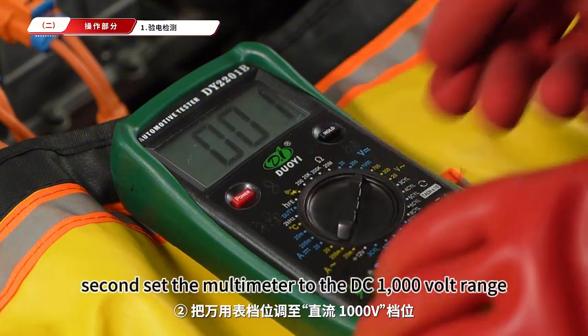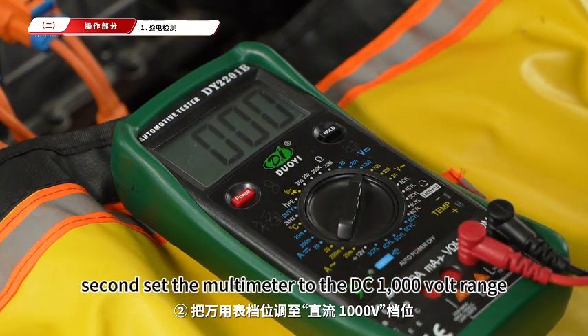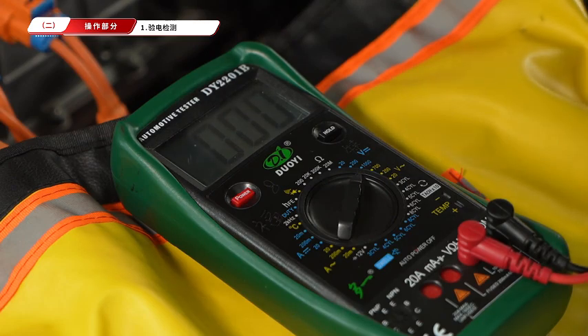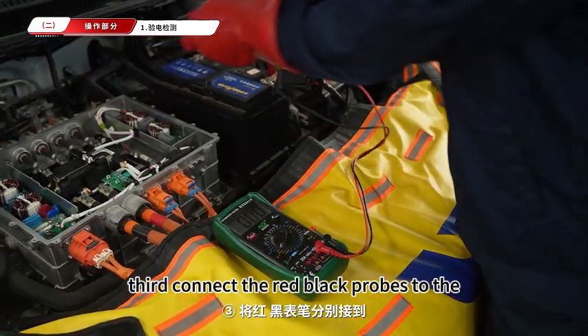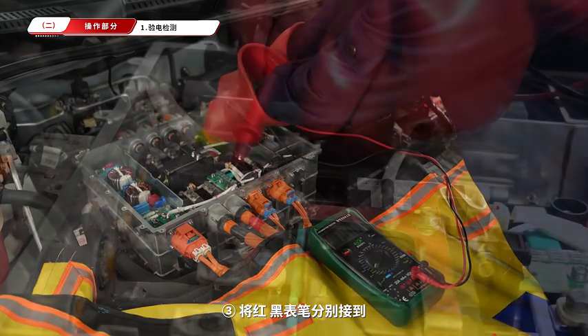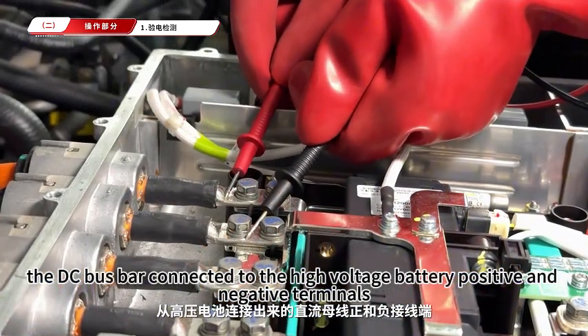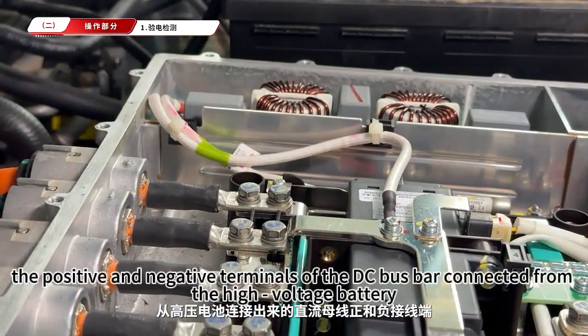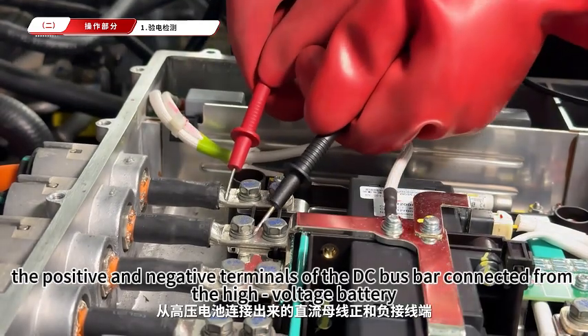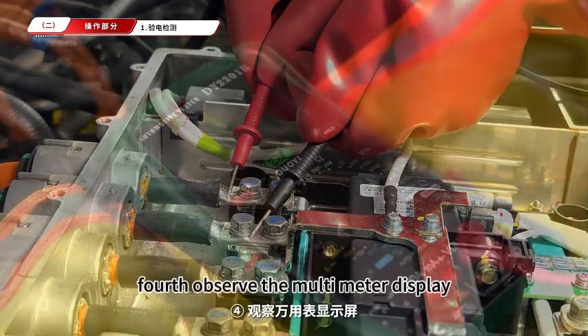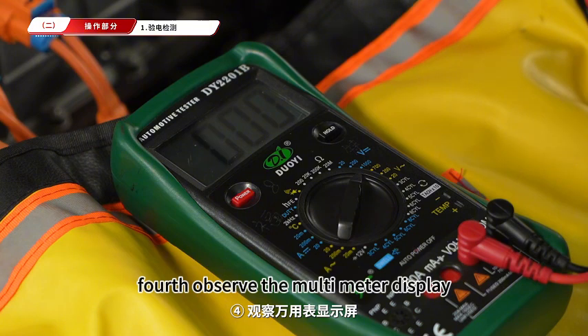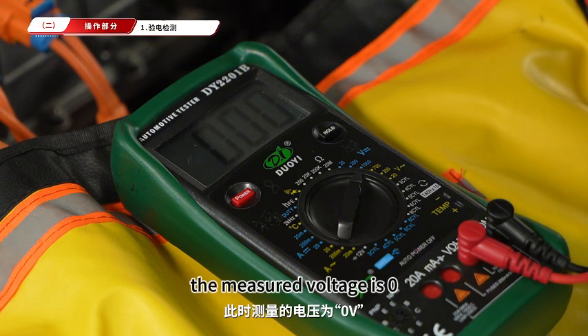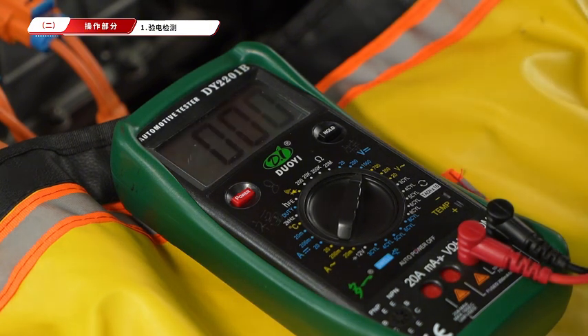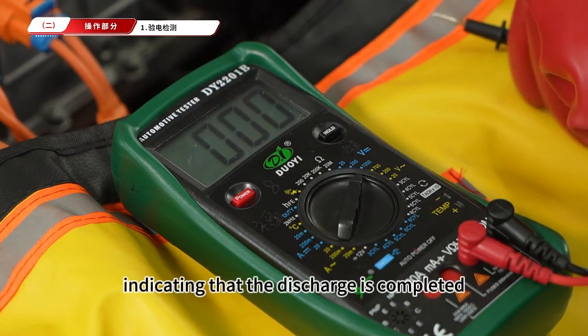Second, set the multimeter to the DC 1000 volt range. Third, connect the red and black probes to the positive and negative terminals of the DC bus bar connected from the high voltage battery. Fourth, observe the multimeter display. The measured voltage is 0 volts, indicating that the discharge is completed.